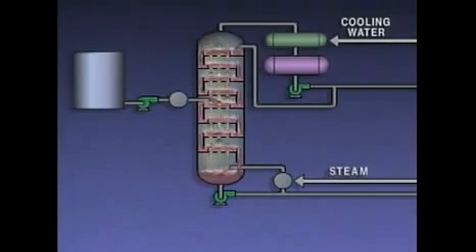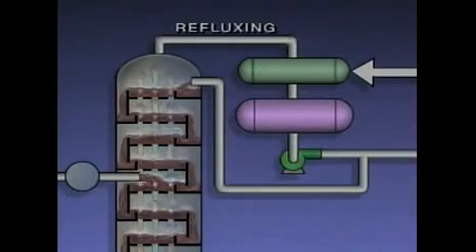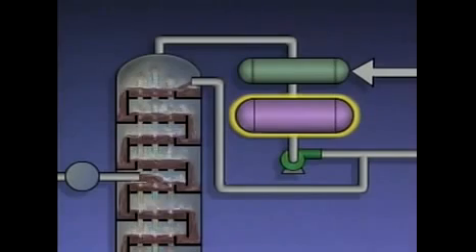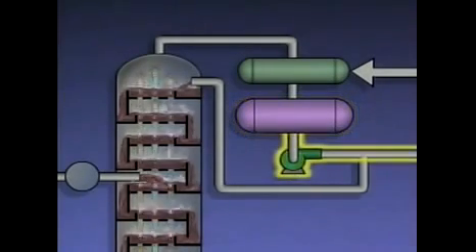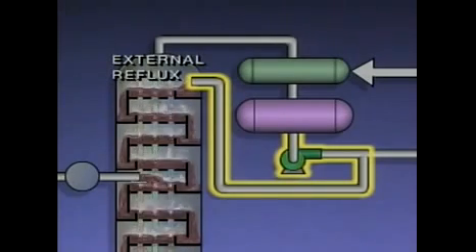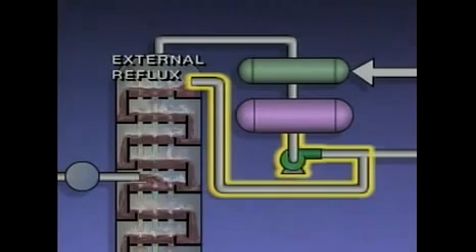Distillation systems use several methods to help maximize the purity of the products. One of these methods is called refluxing. The vapors coming off the top of the tower are condensed in a condenser and then collected in a receiver. Part of the liquid from the receiver is sent to storage or to other units in the plant as the tower's overhead product. The rest of the liquid is pumped back into the top of the tower. The liquid that's reintroduced into the tower is called external reflux.